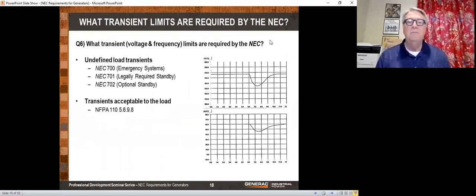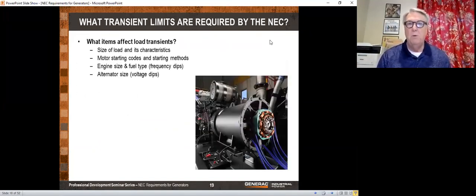Question 6 is an easy one. What transient limits are required by the NEC? In other words, how much voltage and frequency drop can you allow? And fortunately, the NEC didn't get in and try to mess this up. They basically just said the transients should be acceptable to the load. I generally say that if you have solid state devices there, you should never allow more than a 15% voltage drop. If you only have relays, which is less and less common these days, maybe you can go to 20%. The generator is fine with 35%, no problem. But it's the loads that are going to have a problem when that voltage dips further. So that's just my opinion on the matter.